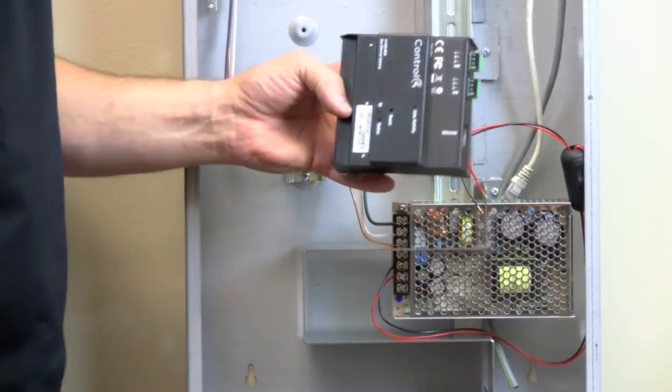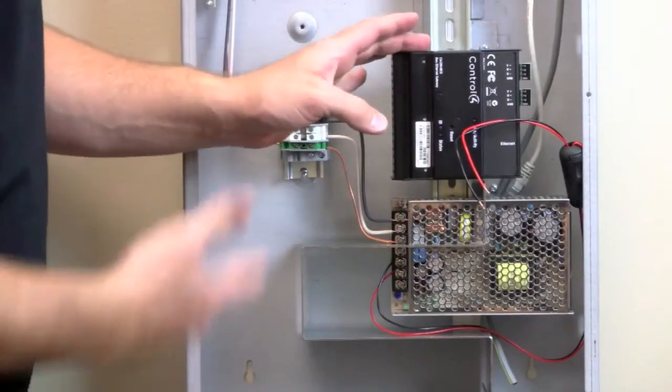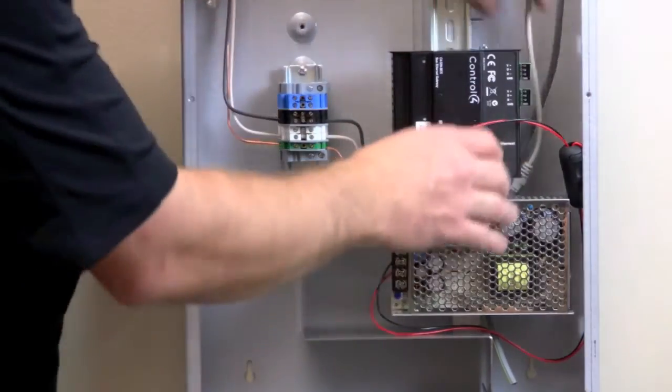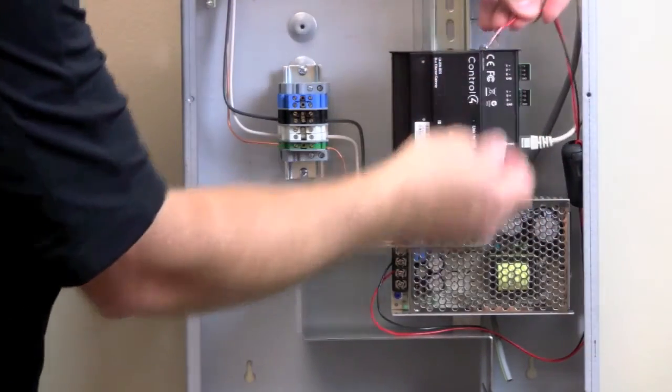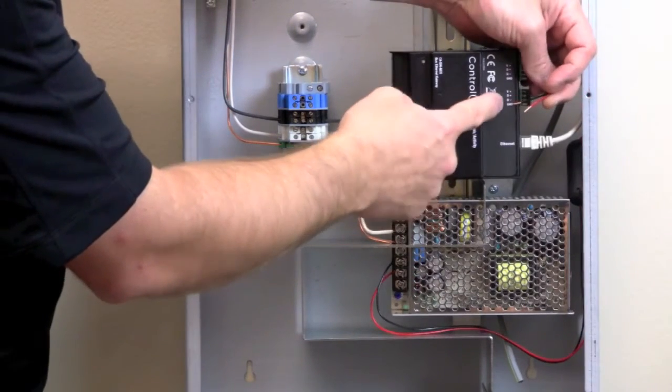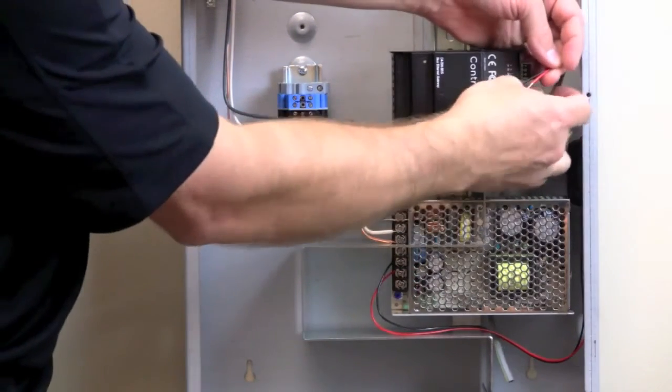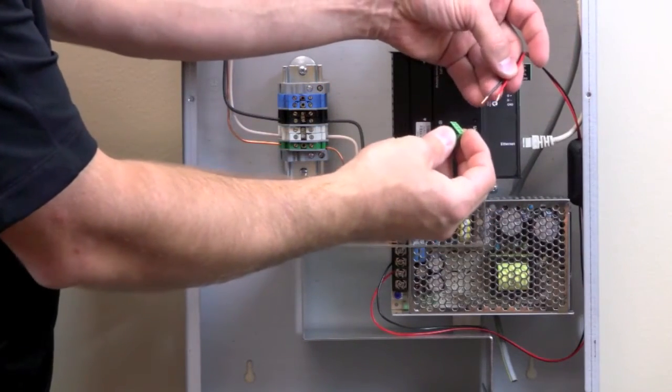Now we're going to mount the bus ethernet gateway by simply clicking on this side and clicking it into place like the rest of the modules. We've got our Cat5 here, let's go ahead and plug that in for communication. And then we're going to take the output of the power supply and connect it to the ground and the voltage plus of the bus ethernet gateway, and then you've powered the bus ethernet gateway.